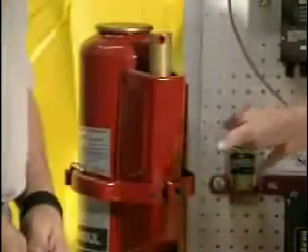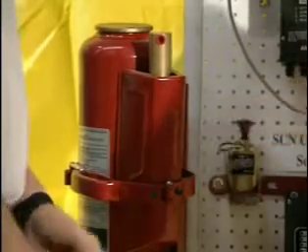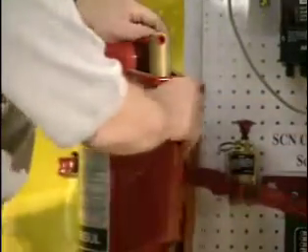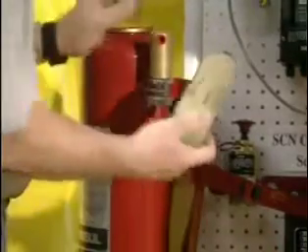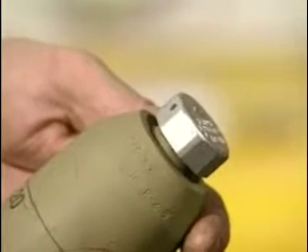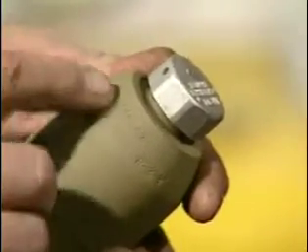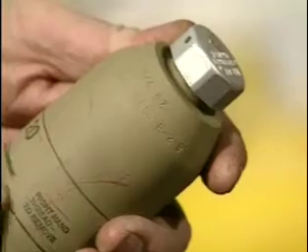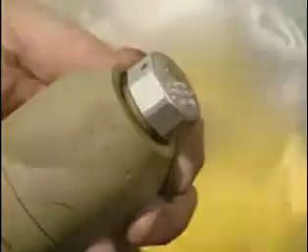Are there any safety concerns that the industry and our industry inspectors need to be concerned about? Yes, this cartridge is a CO2 cartridge, like we talked about. It's got 900 psi. For any one of the cartridges on these systems, you need to weigh them. They should be within a 1/4 ounce of their weight stamped on the cartridge. It's usually stamped all around the top. Sometimes on the smaller ones it'll be stamped in the center. But there'll be a stamped weight on the cartridge. That weight includes the cap.